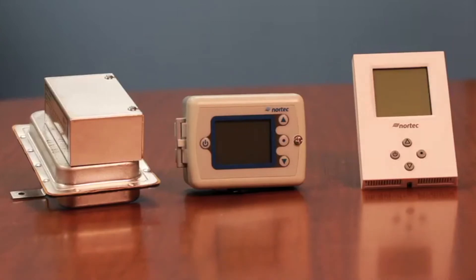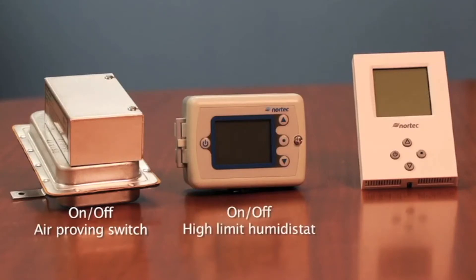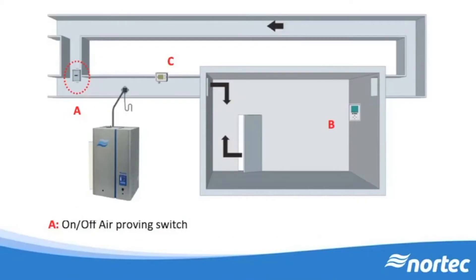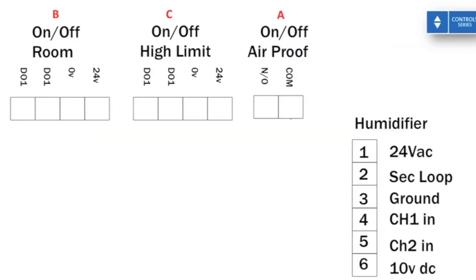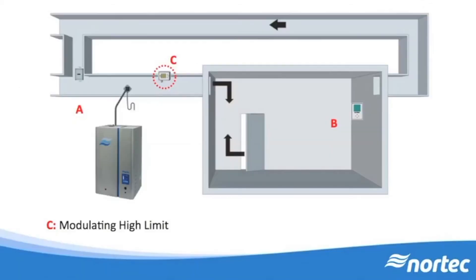Next, let us consider the following three specific devices: an on-off air proving switch, an on-off high limit humidistat, and an on-off room humidistat. The on-off air proving switch wires to the humidifier security loop, leaving the humidifier on pin 1, reaching the common pin of the air proving switch, and when there is airflow, closing the connection across the common and the normally open contact, which is then wired to the next on-off device in the loop — the high limit.